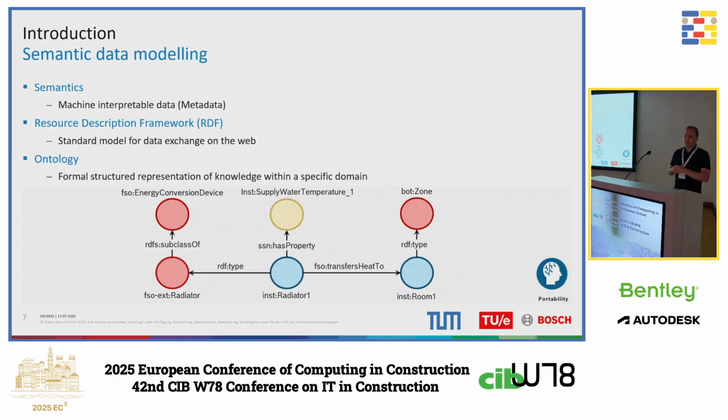Another issue was the portability. So we want to deploy it on a whole building with just one click. We don't want to configure it manually, but we want to have an automated way to deploy these Gaussian processes to different rooms. Therefore we use a knowledge graph from the building where we have the room and associated with it all field actuators and all sensors, so we can query when we want to deploy a Gaussian process which actuators and sensors are relevant for that zone.